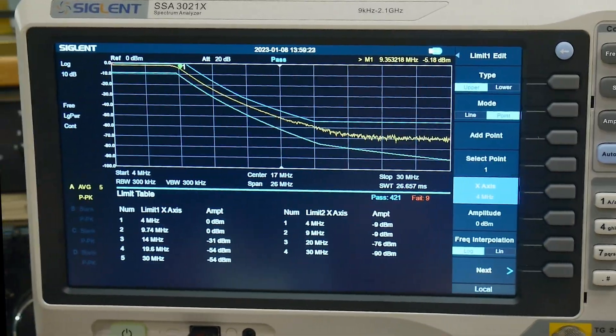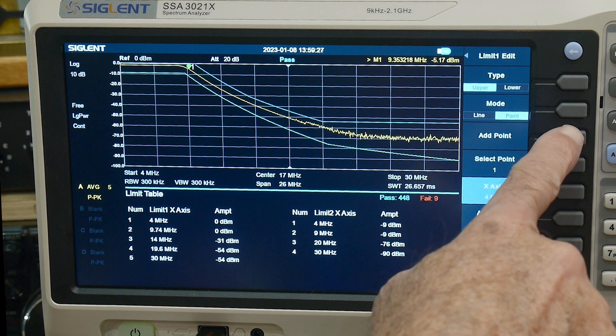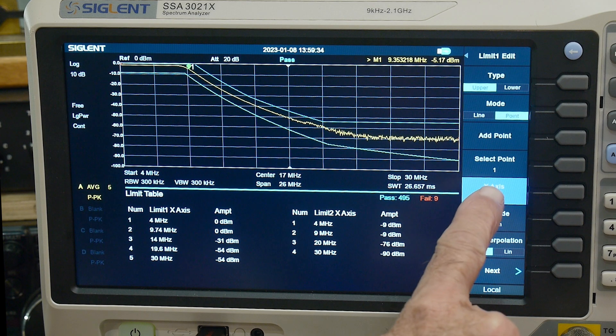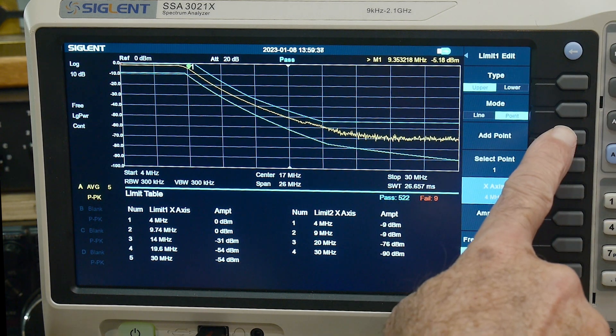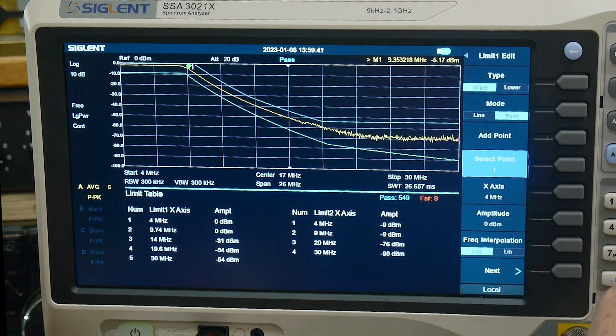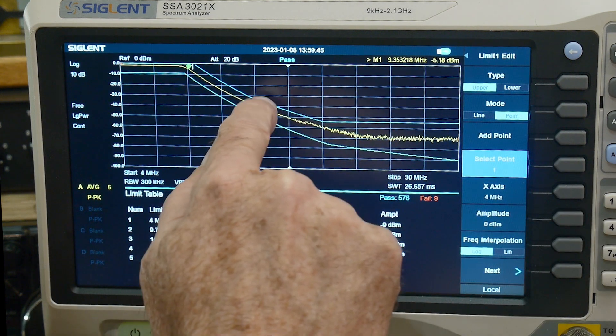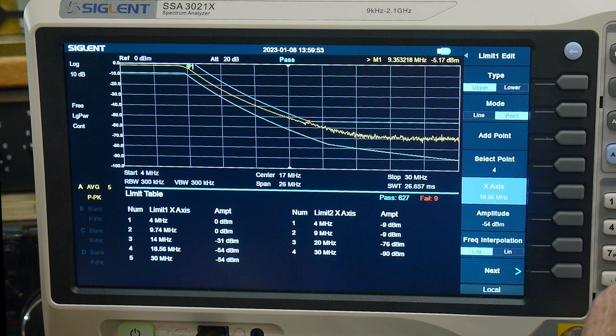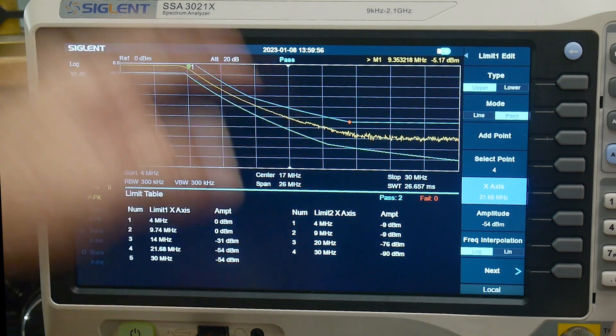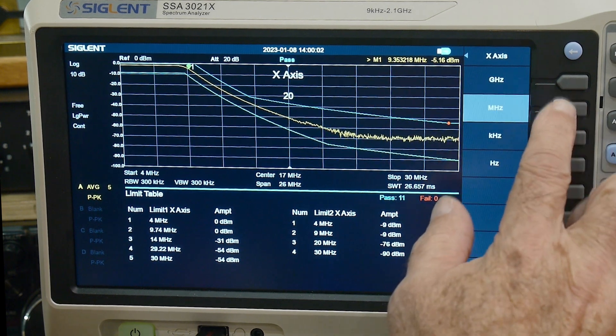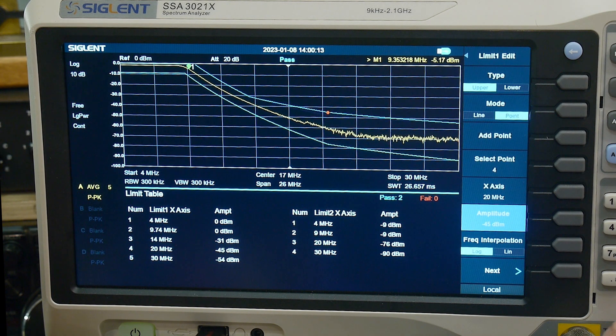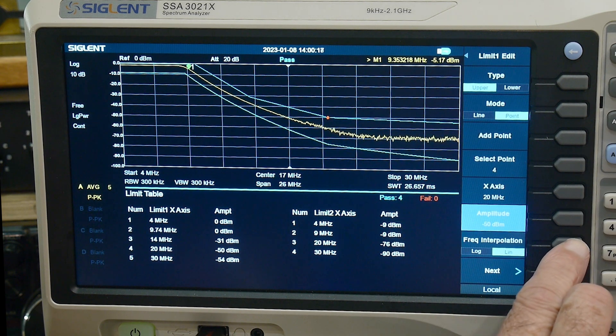Let me zoom in a bit more. You can add a point or select a point, and for each point you enter the X value (frequency) and Y value (amplitude). For example, select point four at 19 MHz — from there you can move the X-axis in and out to change the frequency, so let's set it to 20 MHz. Then you can adjust the amplitude up or down.